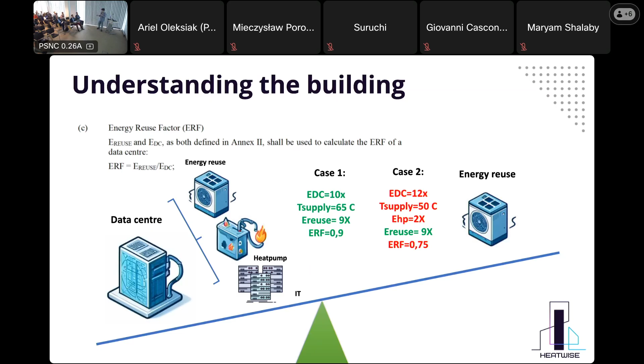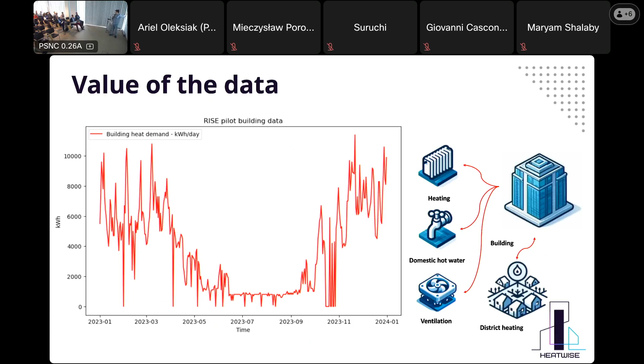This graph represents our building's heat demand through the year. During wintertime, it's around -20, -30 degrees outside, and the heat demand significantly increases. It's a warehouse where multiple companies are using it, and we use it to run our data centers. During summertime, as you can see, the demand is minimized. So what can I do with this data to improve my data center operations?